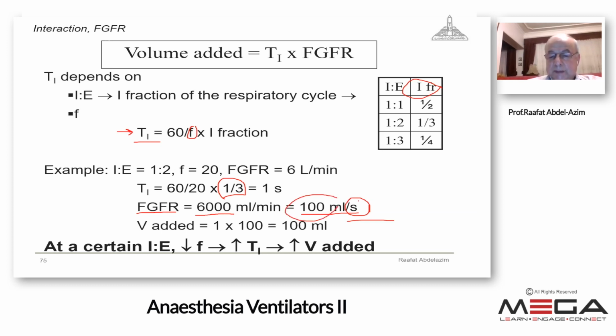Calculate the inspiratory time, and the product of this addition times the inspiratory time will give the part of the fresh gas flow that goes into the inspiratory limb. The volume added here, in this example of having 1 second inspiratory time and 100 milliliters per second of the fresh gas flow rate, gives 100 milliliters per breath added to the tidal volume.